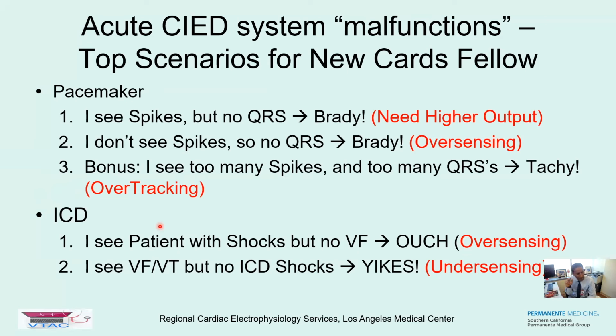So you're not worried about pacing as much, although it will inhibit pacing. Especially if the patient is pacer dependent with a defibrillator, now you've got a double whammy - they'll stop pacing and they'll get a shock. In fact, if a pacer-dependent patient gets a shock and says they passed out with an ICD, that doesn't mean it was VF, because it could be oversensing. They were pacer dependent, it stopped pacing, and it shocked them. So you still have to check the device.